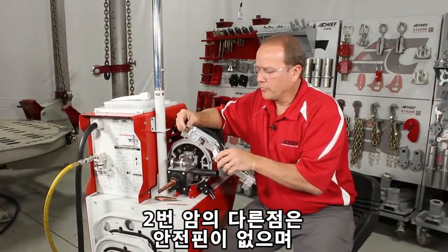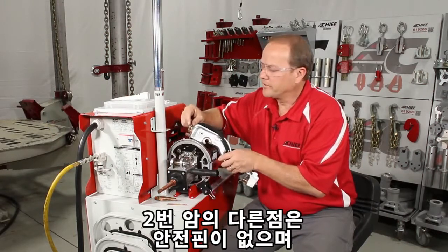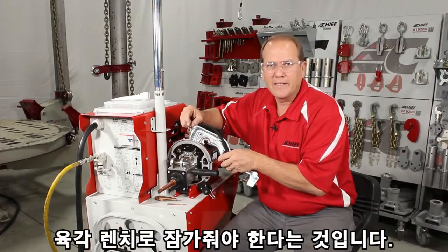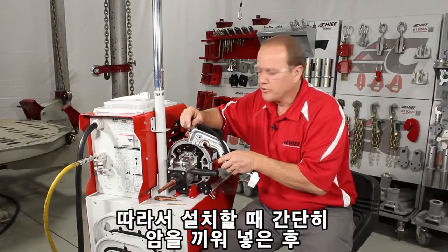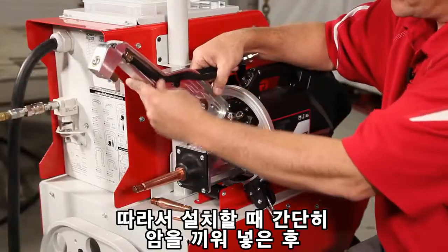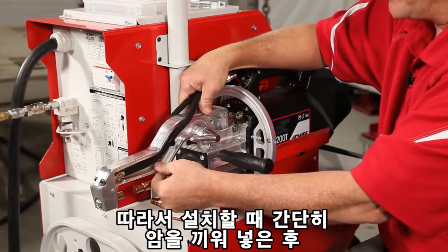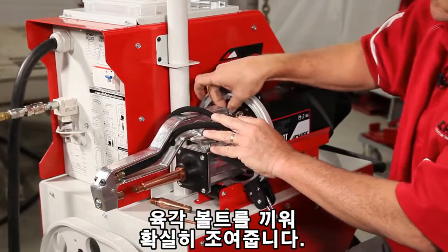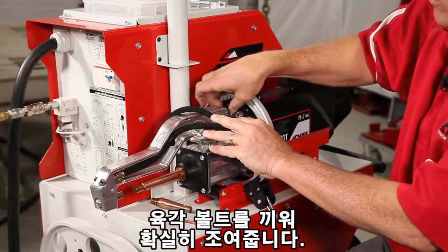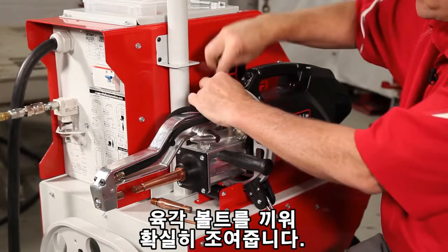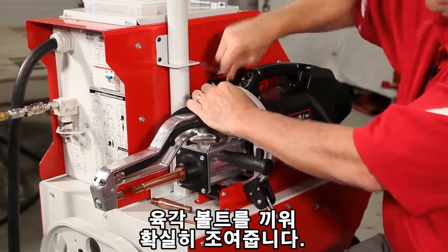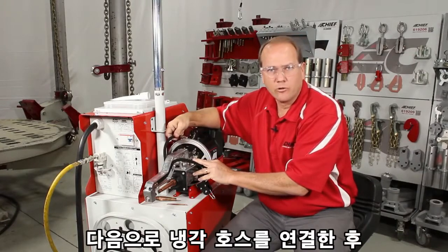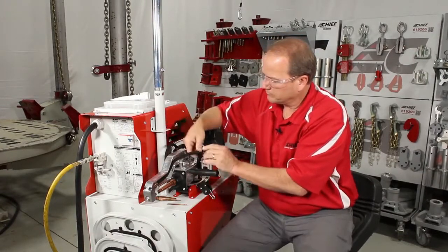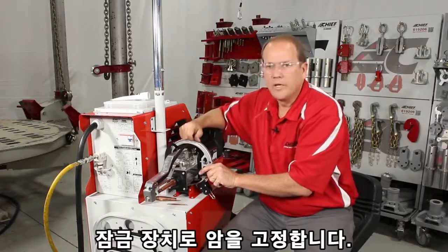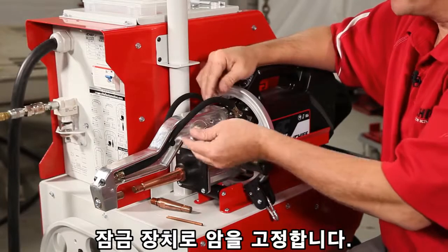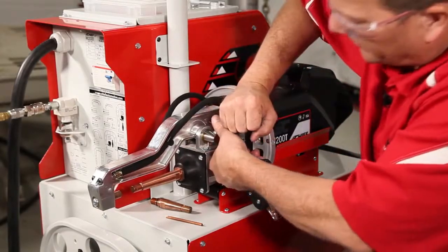The one thing that's different with this number 2 arm is it does not have a safety pin. It has an Allen wrench to lock in place. So to install, we're going to simply engage the arm, drop it down, take the Allen and screw that down and make sure it's snug. And then engage the coolant lines. And then now we're going to lock using the lock mechanism on the arm.